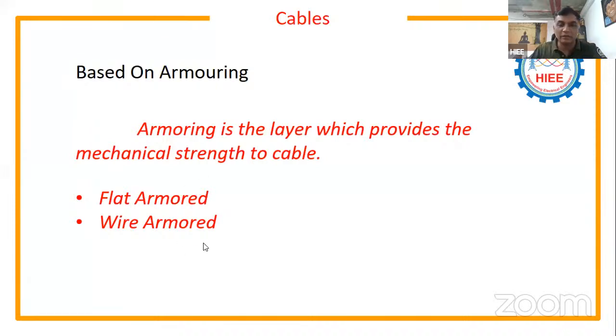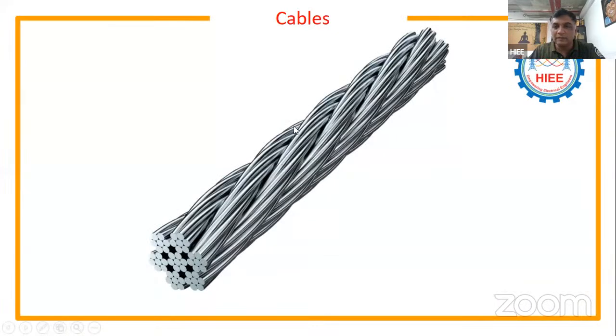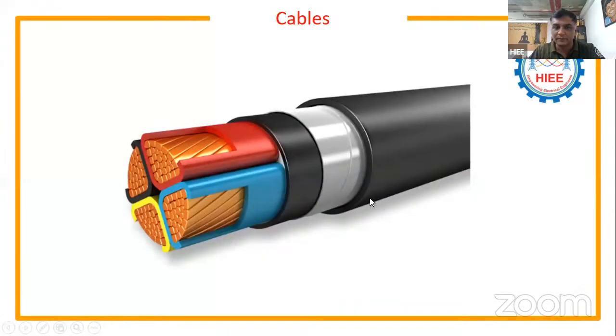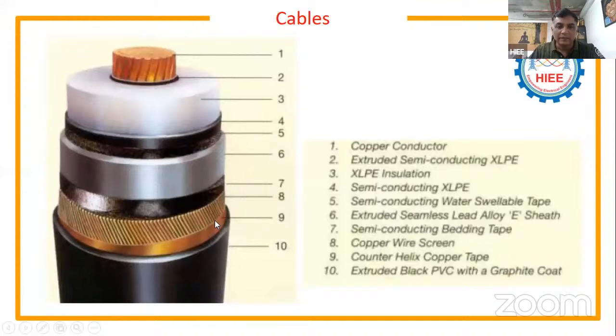So now coming to the point, we have two types of armoring we use for cables. One is flat armored and the other is wire armored. So this is the conductor. Here I have shown you one cable now. This armoring is called flat armored, and this cable is a wire armored cable. You can see here, this one is the conductor. On top of that you have an extruded semiconductor XLPE sheath.